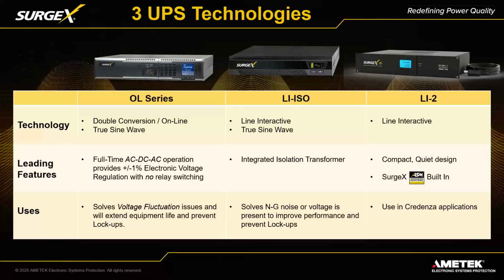But as Vince's illustration points out, that dedicated 20 amp run is going to go back to that sub panel or mains panel, and then it's all intertwined with whatever else is tied to that ground—neutral and ground are all bonded together. So hopefully it's a dedicated 20 amp run; it will probably be cleaner than if it were coming off a ceiling fan load or a lighting fixture.